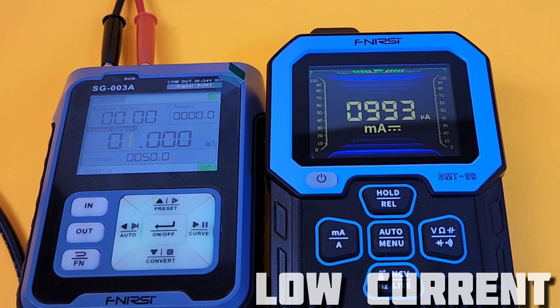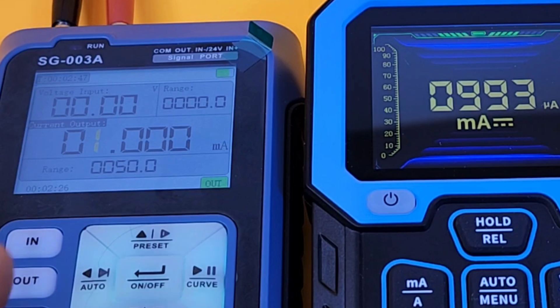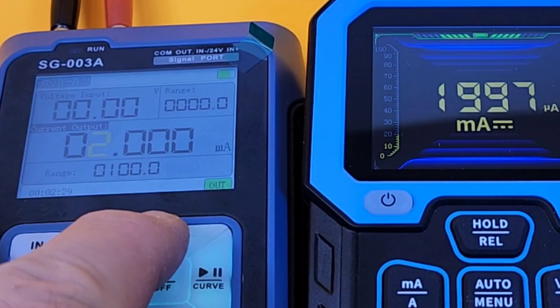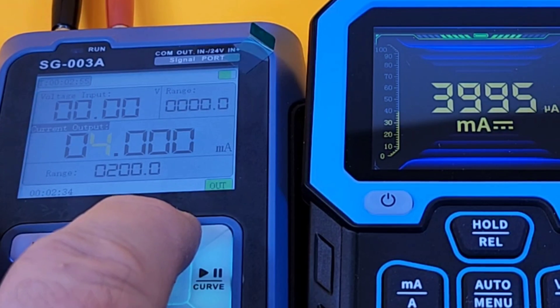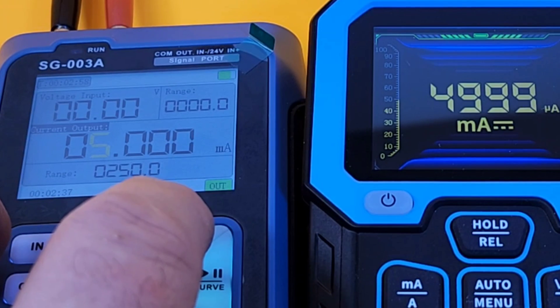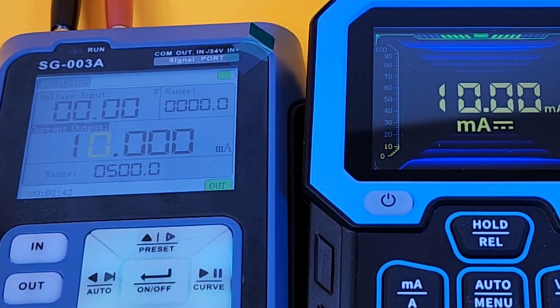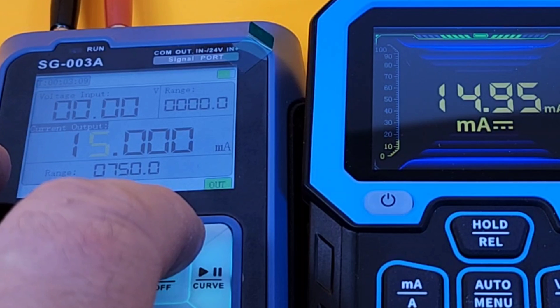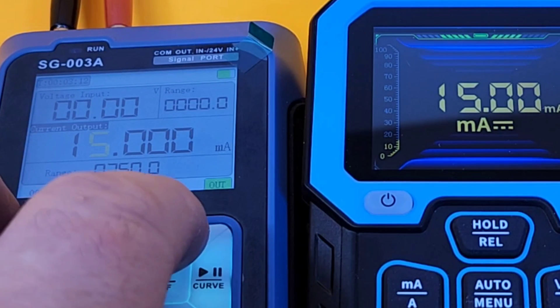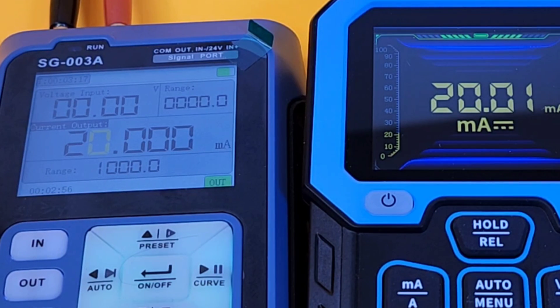Quick peek at milliamps — sitting at one milliamp. Let's bring it up to two milliamps: coming in as 1.997 on the DMT-99. Four milliamps: coming in at 3.995. 15 milliamps — so close. 10 milliamps: spot on. 20 milliamps: spot on. We'll max it out now at 20 milliamps — and that's a booyah. Good stuff.